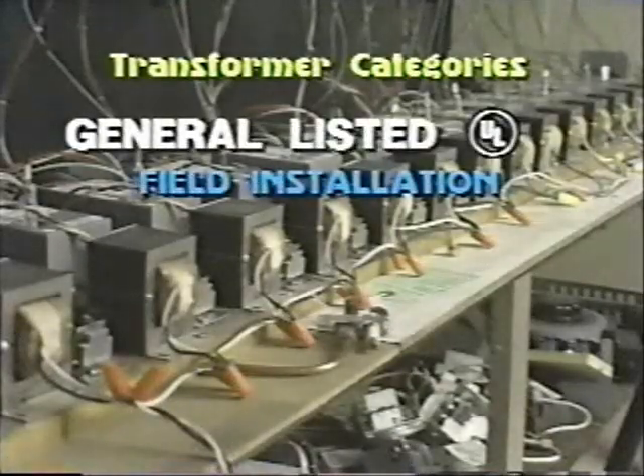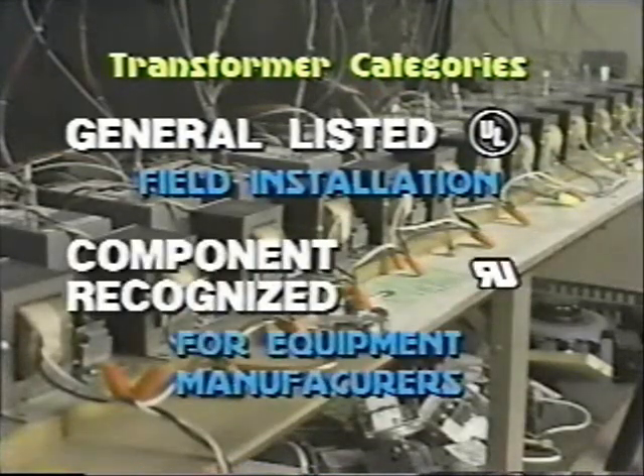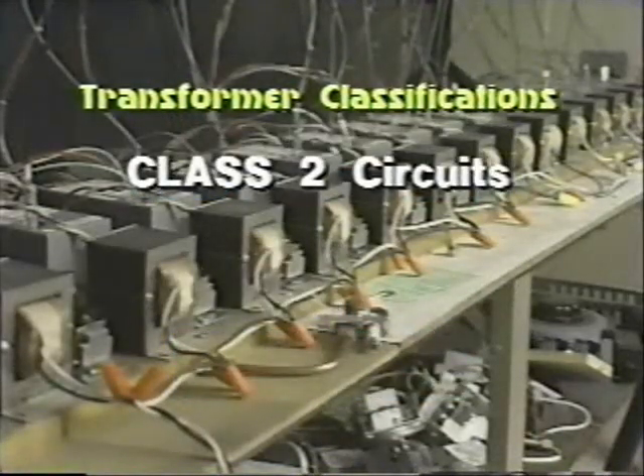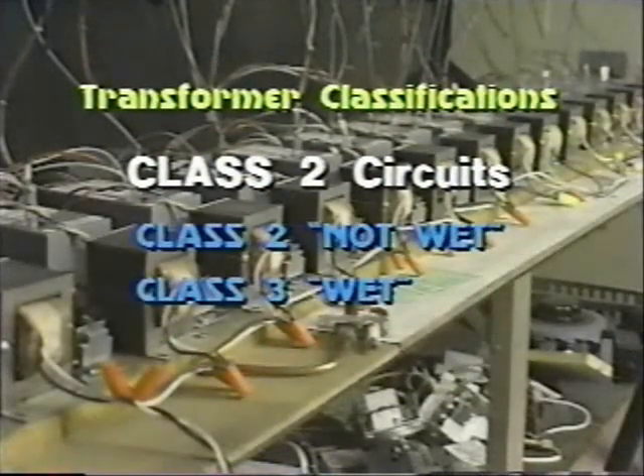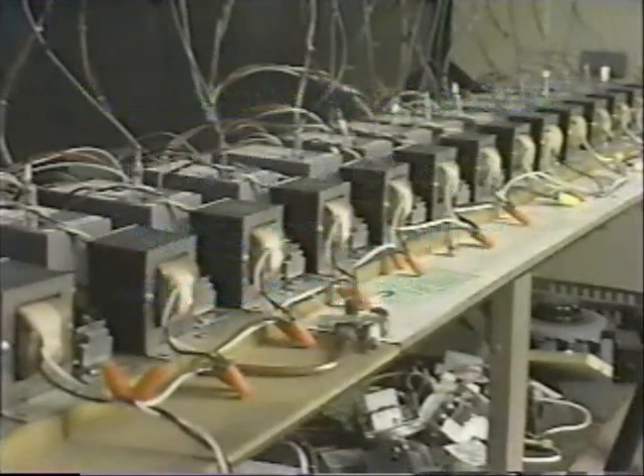There are two categories of transformers. General listed transformers are suitable for field installation. Component recognized transformers are designed primarily for use by equipment manufacturers. NEC classifies transformers for Class 2 circuits as Class 2 not wet and Class 3 wet. Essentially, these classifications define where a transformer may be safely located in terms of its exposure to moisture.